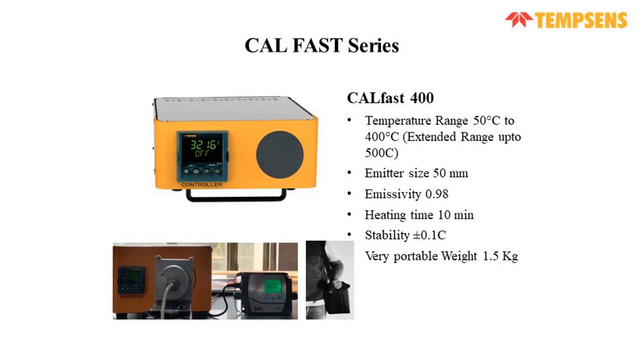Like Calfast 120 and Calfast 350, we have Calfast 400 in the black body models. The temperature range for Calfast 400 is 50 to 400 degrees centigrade, and it can be extended up to 500 as per the needs of the customer. The emitter size is 50 and the emissivity is 0.98. The heating time is 10 minutes, with a stability of plus minus 0.1 degree centigrade. It is very portable and weighs very little, about 1.5 kgs.